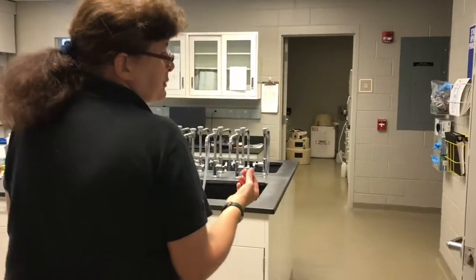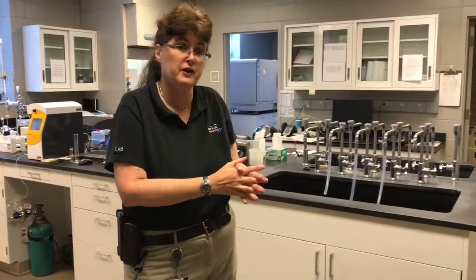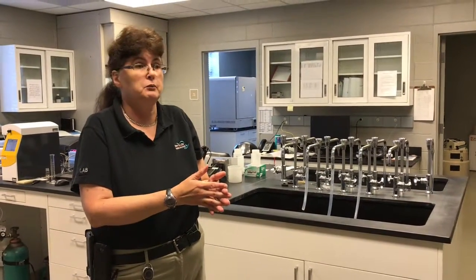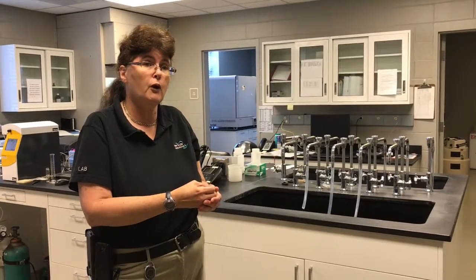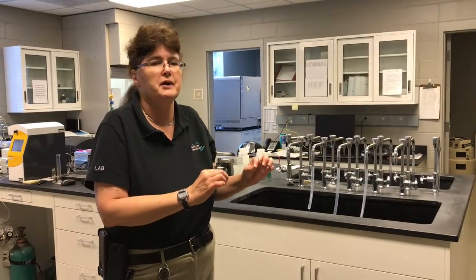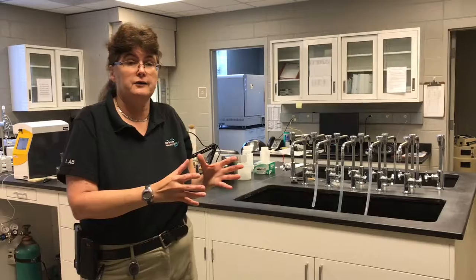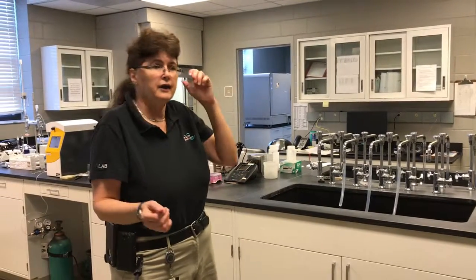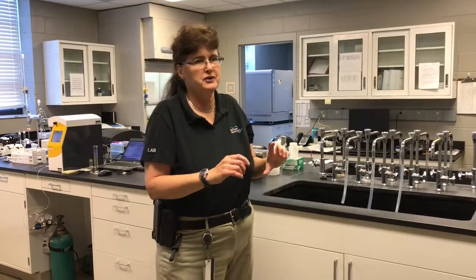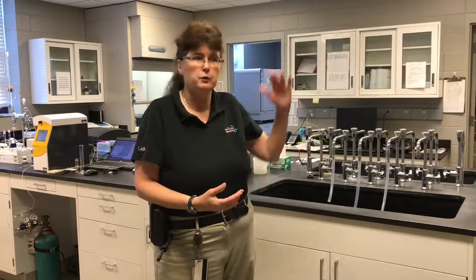We also do the EPD testing for lead and copper, all these different requirements by federal law. We collect the sample bottles and send them off to the Georgia EPD lab in Atlanta, and they do the actual testing. But we are the ones who run around and pull all the samples in a precise manner. Some samples have to be collected with zero headspace, so you have to make sure you have the technique down to collect it so there are no air bubbles in it. We do that to meet all the federal requirements.